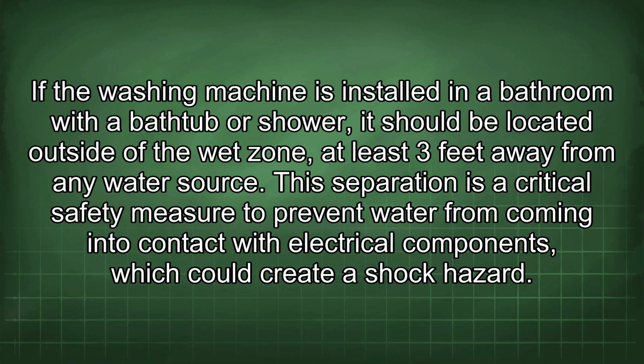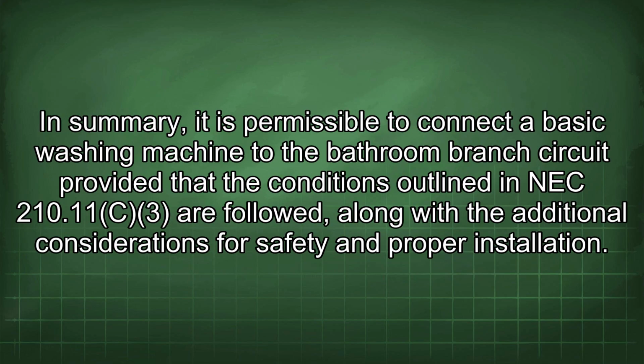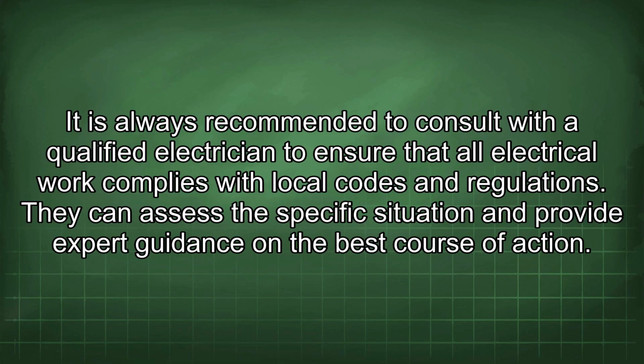This separation is a critical safety measure to prevent water from coming into contact with the electrical components, which could create a shock hazard. In summary, it is permissible to connect a basic washing machine to the bathroom branch circuit provided that the conditions outlined in NEC 210.11c3 are followed, along with the additional considerations for safety and proper installation. It is always recommended to consult with a qualified electrician to ensure that all electrical work complies with local codes and regulations. They can assess the specific situation and provide expert guidance on the best course of action.